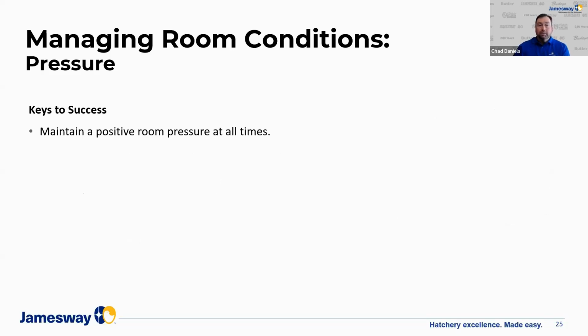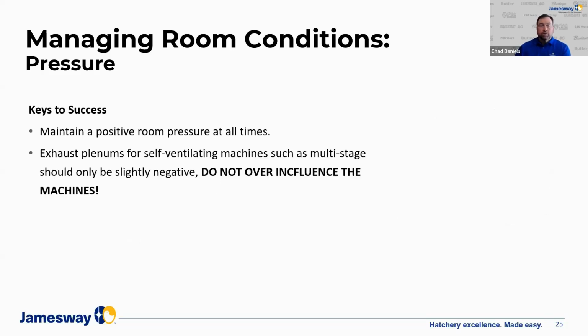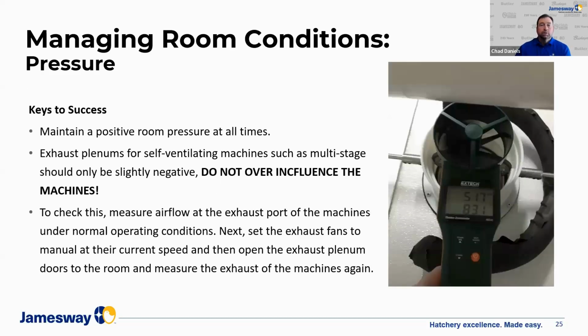So maintain a positive pressure at all times. Exhaust plenums for self-ventilating machines, such as Multistage, should only be slightly negative. Do not over-influence the machines. And to check this, measure airflow. In this illustration, I'm using a handheld Extech anemometer, and I'm measuring airflow from the machine.